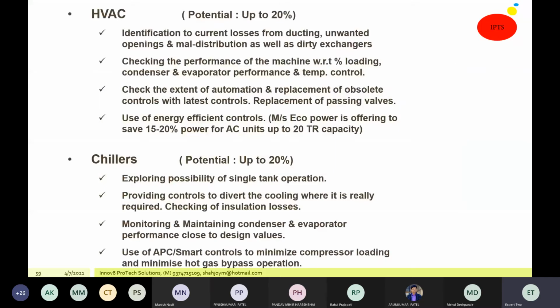HVAC is normally used in most of the control room buildings for air conditioning and air quality control. And we found that air distribution is always inefficient. There are dirty exchangers, and proper temperature control is not provided. So all these areas can be improved so that your energy consumption can be reduced.